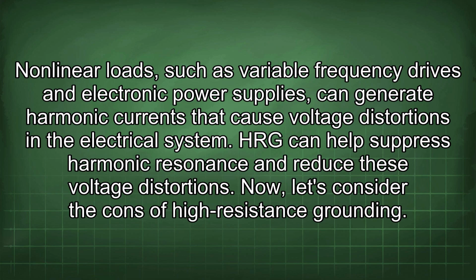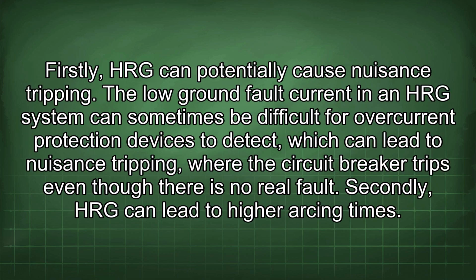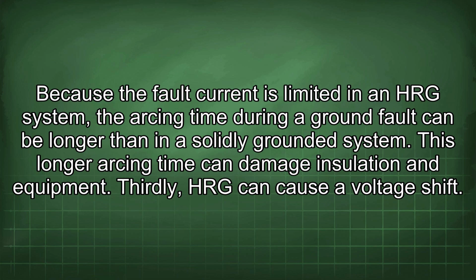Now let's consider the cons of high resistance grounding. Firstly, HRG can potentially cause nuisance tripping. The low ground fault current in an HRG system can sometimes be difficult for overcurrent protection devices to detect, which can lead to nuisance tripping, with the circuit breaker tripping even though there is no real fault. Secondly, HRG can lead to higher arcing times. Because the fault current is limited in an HRG system, the arcing time during a ground fault can be longer than in a solidly grounded system. This longer arcing time can damage insulation and equipment.